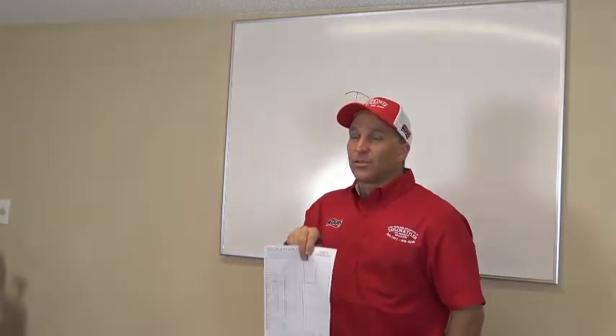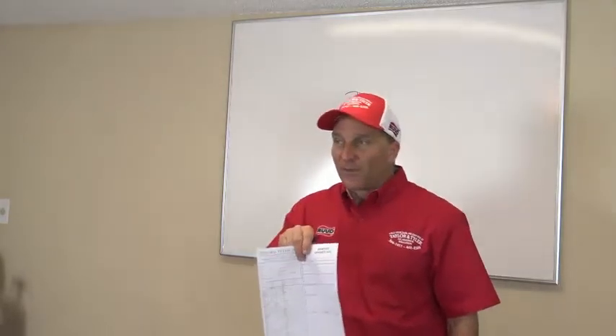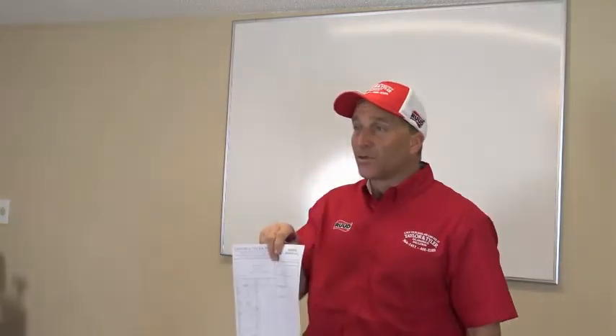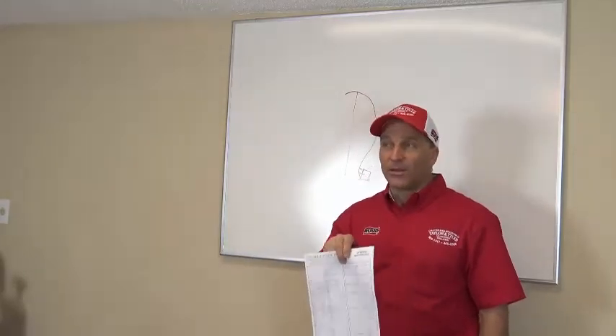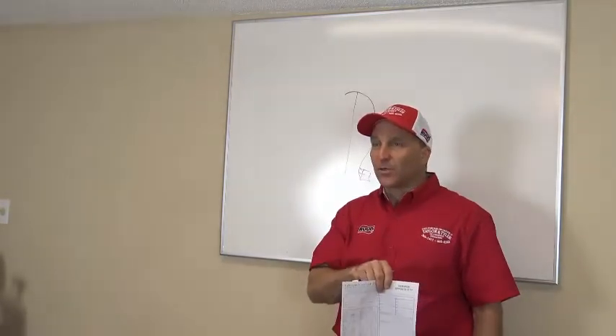Okay? Well, Eric also told you that your superheat should be about 15. It is. Eric also told you that an ideal coil temperature is 40 degrees, and you're reading 35. It's low. And if you let refrigerant out, you're going to drop your suction pressure. You're going to drop your head pressure. Well, if you looked at your condenser, your head pressure is already low. Now you let refrigerant out.